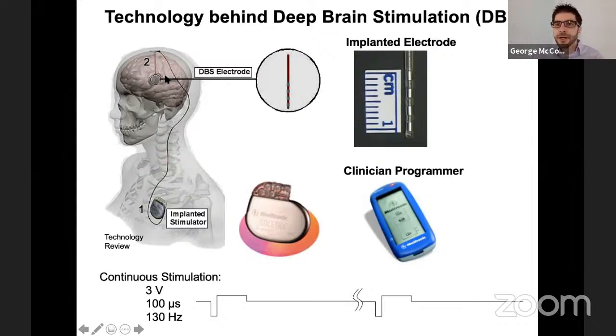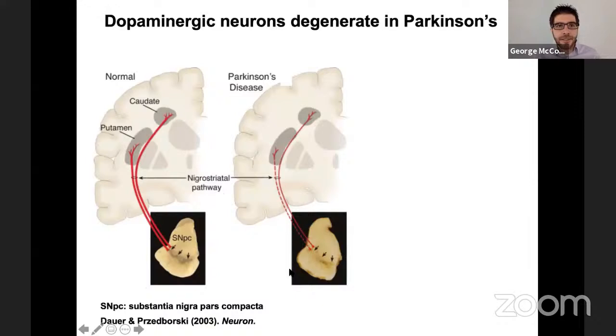And the idea, much like a cardiac pacemaker, is that the pathological rhythms in the brain are overridden by these electrical pulses, just like in a cardiac pacemaker where arrhythmias in the heart are paced over by the electrical patterns delivered. This is an example of the Medtronic's design of 4 electrodes, and a clinician programmer can wirelessly program the settings on these DBS electrodes to control the stimulus waveform, including the amplitude of the pulses delivered, the duration of these pulses, as well as the timing between pulses.